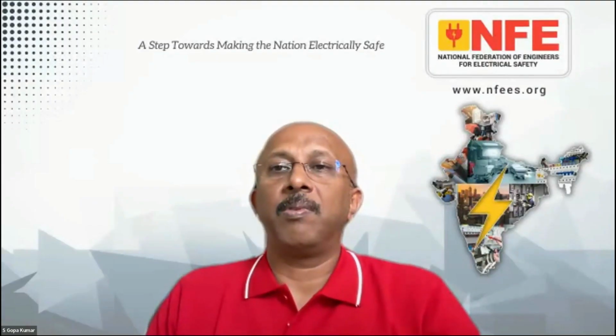See, this is a very interesting subject because very often, when you come to selectivity, it's very important to have this coordination done. But sometimes in installations, people use MCBs to do switching. What will happen is you lose selectivity in this case. What you need to do is use an isolator there.